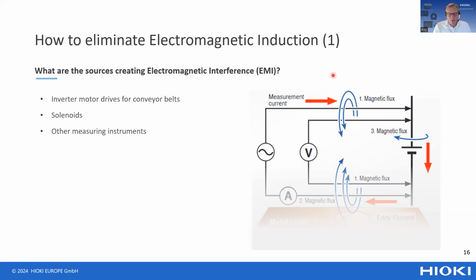At low ranges, this measurement current is quite high. At the 3 milliohm range of the battery tester, the current we are generating is around 1 amp. This current causes a magnetic flux, shown with the blue arrows, that can influence the voltage sensing of the measurement instrument and causes a problem with the accuracy of the measurement.